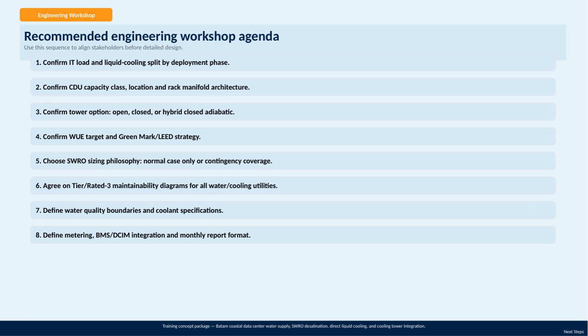Then, we'll verify the cooling distribution unit capacity, its location, and the architecture for the rack manifold to optimize efficiency. We must also decide on the type of cooling tower, whether it will be open, closed, or a hybrid closed adiabatic system, as this impacts performance and sustainability. Setting the water usage efficiency target and aligning with Green Mark or LEED certification strategies is a priority to meet our environmental goals. Our seawater reverse osmosis system sizing needs to be established, determining if we design for normal operational conditions only or include contingency coverage for resilience. Agreeing on tier or rated 3 maintainability diagrams for all water and cooling utilities will ensure high reliability and maintainability standards.